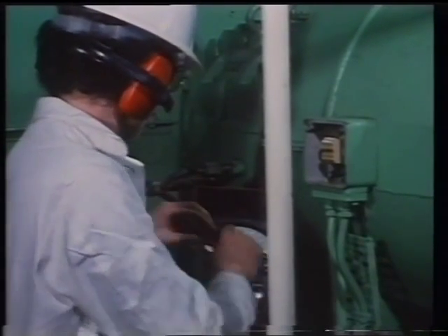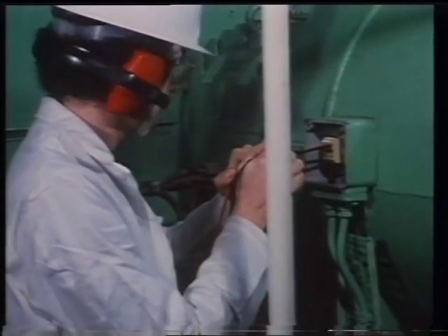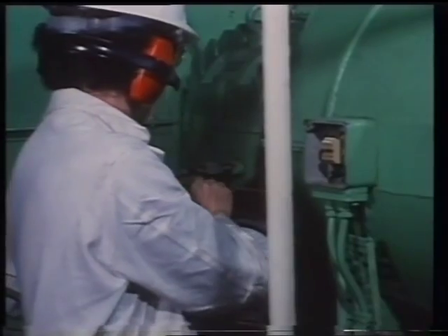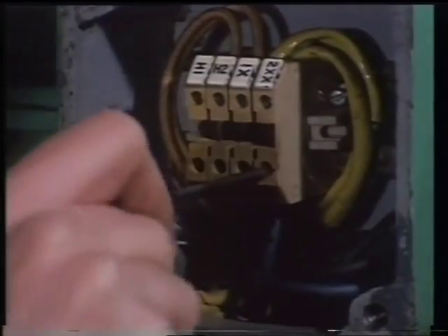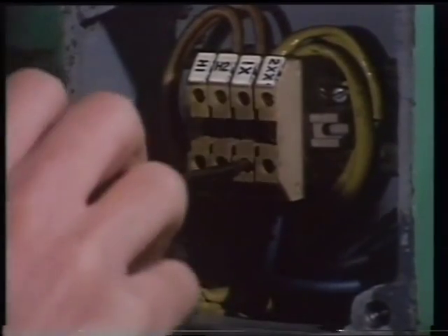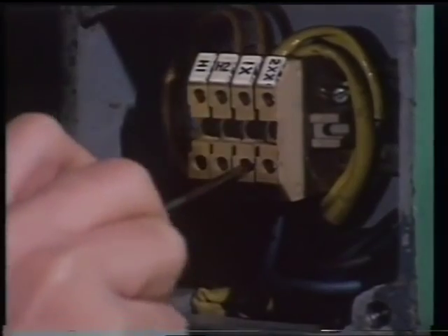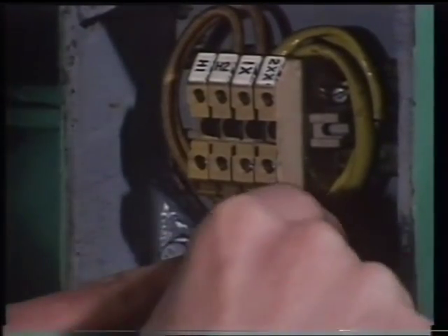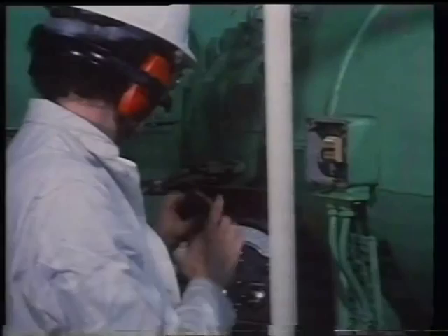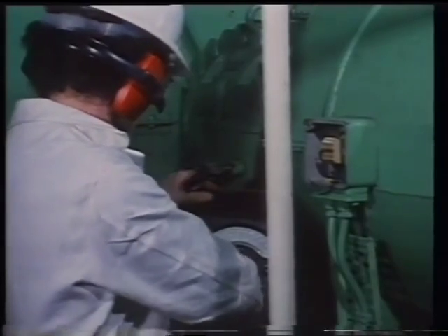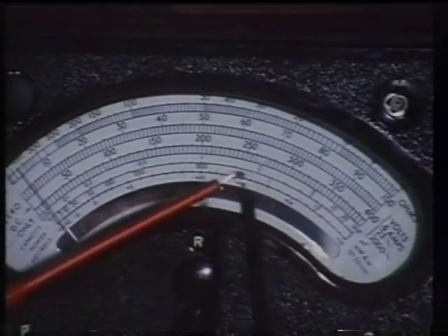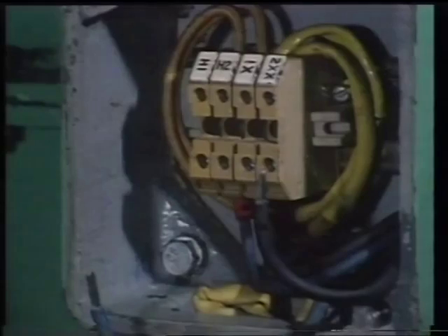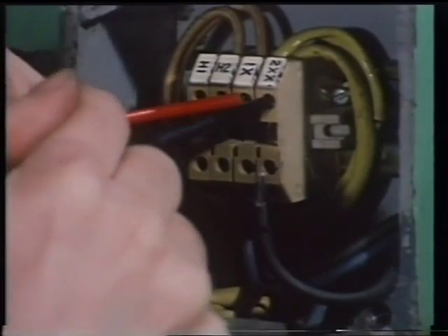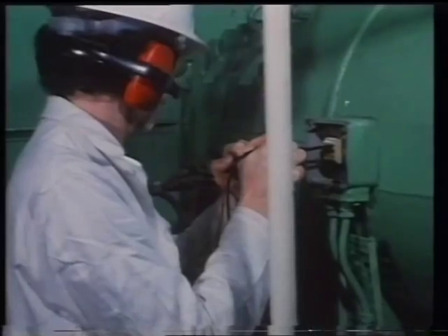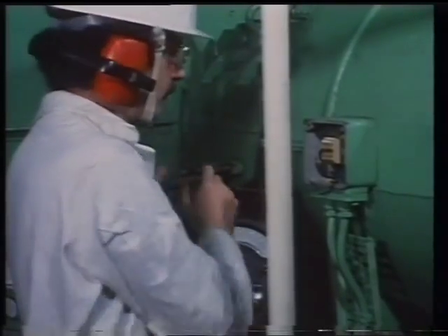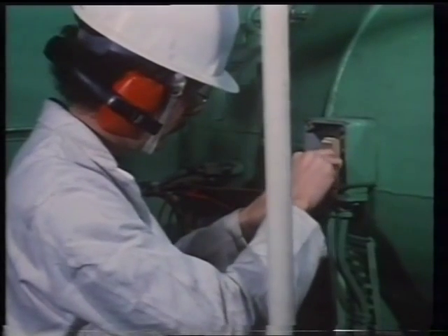Testing for open circuit fault can be done with a multimeter. The procedure here is, first check that the circuit is dead using the multimeter set to read voltage. Then disconnect the feed wires from the coil ends, making a note of the color coding of the wires so that they can be reconnected correctly. Then set the meter to read resistance. The test can then be done, testing the meter first, then the terminals. The reading shows good continuity. A break in the continuity would have left the pointer at infinity. Now the contacts are remade and the terminal box closed.